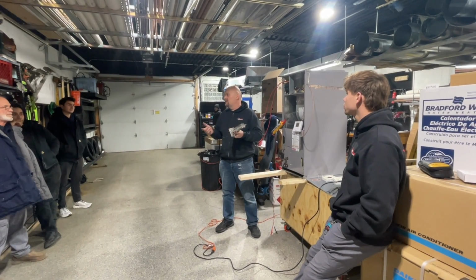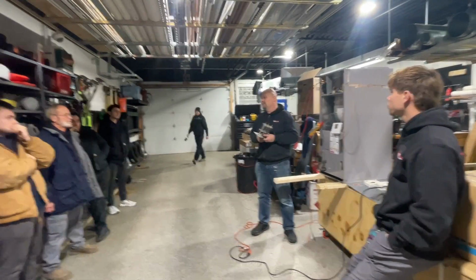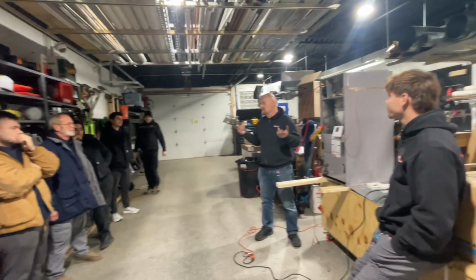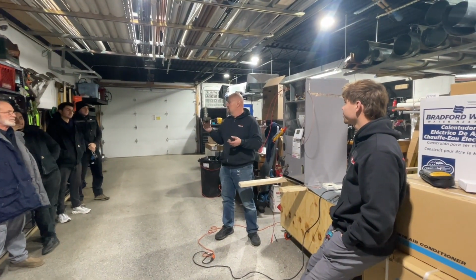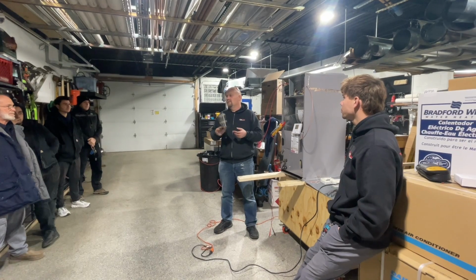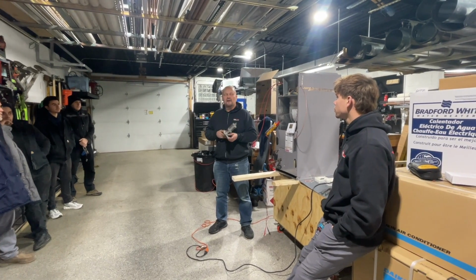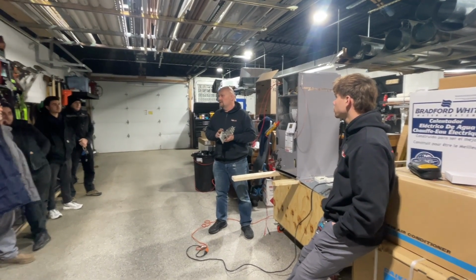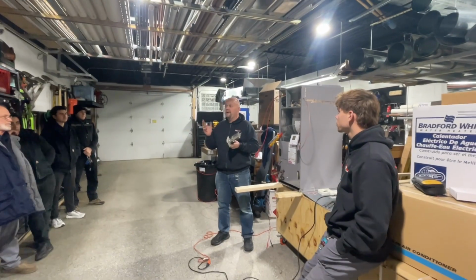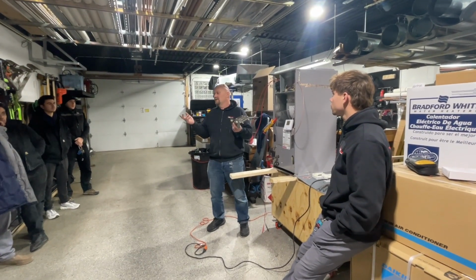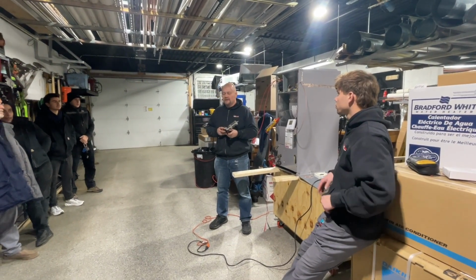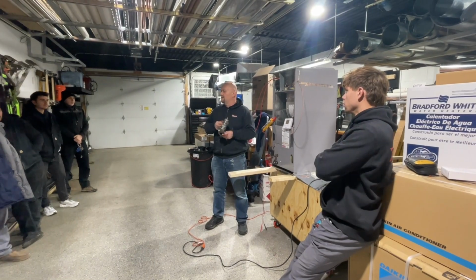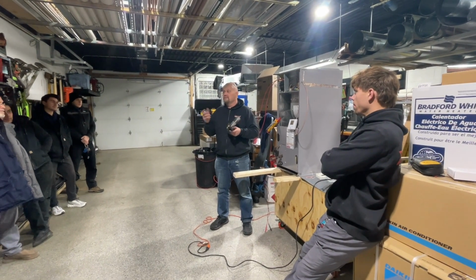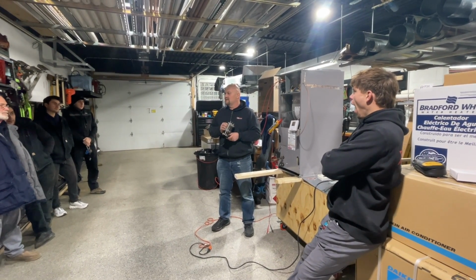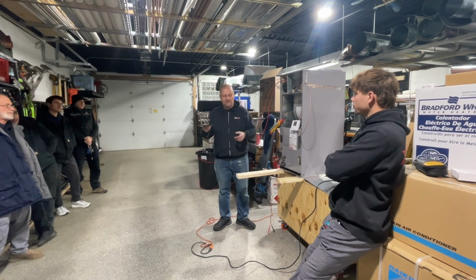So, and it's okay to replace it and not have a person worry about it. This burns. This is basic controlled electrical fire. So another thing to make sure is nothing ever falls on top of this. If you have a humidifier, make sure the pad doesn't go in there. Obviously, the humidifiers we put in are fine. A few times I found a piece of plastic fall into it, melts. It doesn't start a fire, but it starts smoke. So this gets really, really hot.